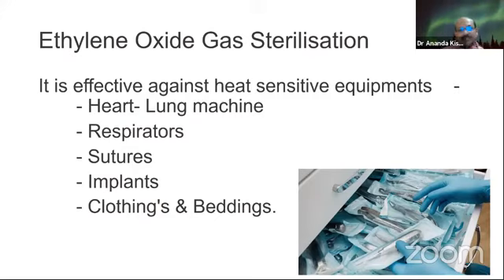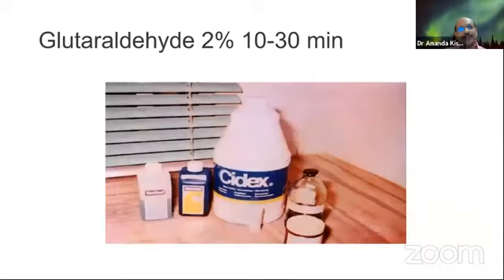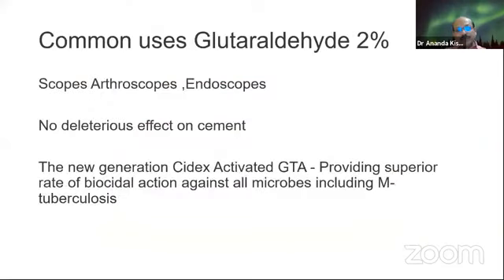Basically, apart from the implants, the other items which can be sterilized this way are heat-sensitive equipment like the heart-lung machine, respirators, sutures, implants, and clothing and bedding. Now, another important quick sterilization is the Cidex. It's very popular among orthopedic surgeons, and basically it is 2% glutaraldehyde. The instrument should be immersed inside this liquid for at least 10 to 30 minutes. It should be a minimum of 10 minutes. The ideal should be 30 minutes.